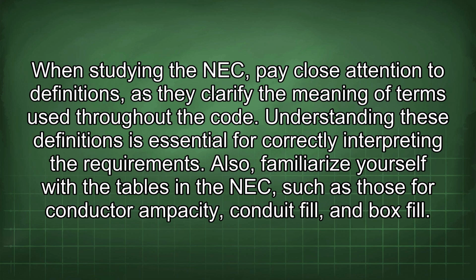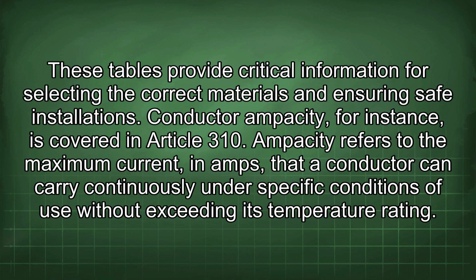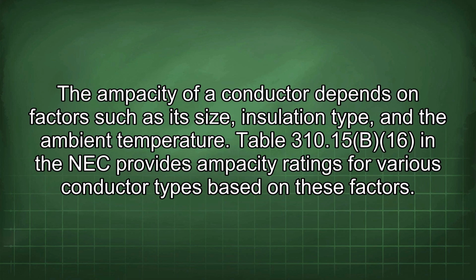Also, familiarize yourself with the tables in the NEC, such as those for conductor ampacity, conduit fill, and box fill. These tables provide critical information for selecting the correct materials and ensuring safe installations. Conductor ampacity, for instance, is covered in Article 310. Ampacity refers to the maximum current, in amps, that a conductor can carry continuously under specific conditions of use without exceeding its temperature rating. The ampacity of a conductor depends on factors such as its size, insulation type, and the ambient temperature.